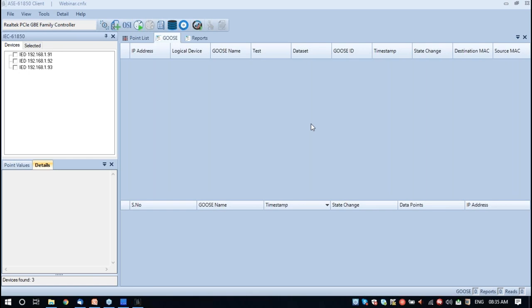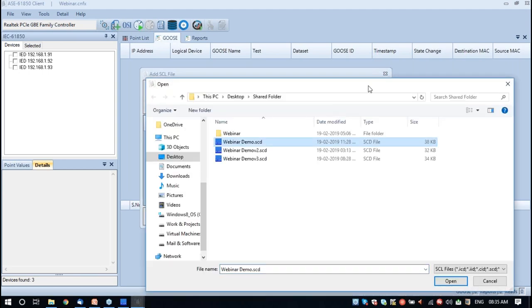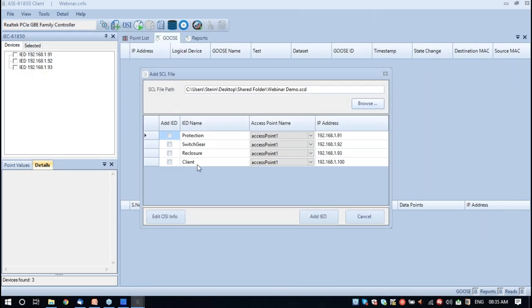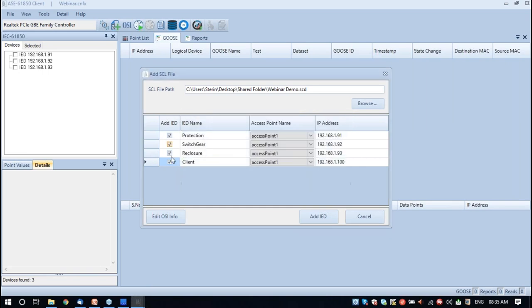I hope you are able to see the client view. The client can be configured in two ways. First, being the SCL file loading — you could load the SCL file here and browse it, and it will list down all the IEDs available in the configuration. An advantage of having a test client is that if you select the test client, it will automatically identify which other IEDs are sending data to the test client. It will automatically select other IEDs sending signals, which will be a handy feature if you want to configure and use this client to communicate with the selected devices.